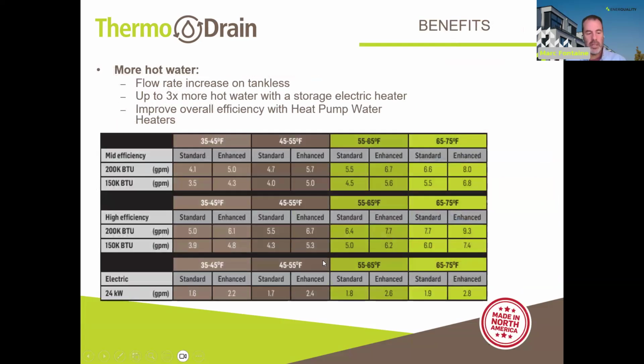So drain water heat recovery collects drain water from mainly the shower and other hot water drain sources. And it now needs to do something with the preheated water it generates. So usually we send it off to a hot water heating device. Drain water heat recovery is compatible with any type of hot water heating device. So this is an example where we have an instant gas-fired water heater.